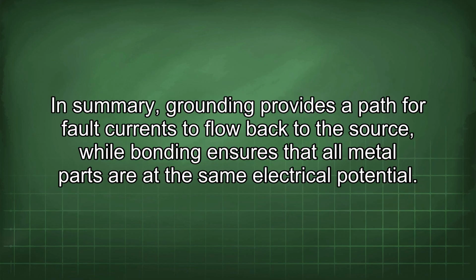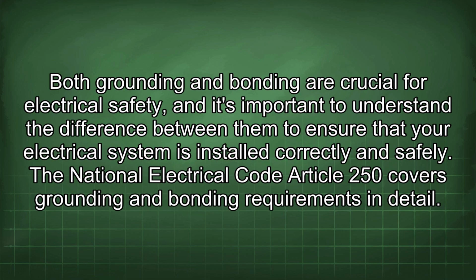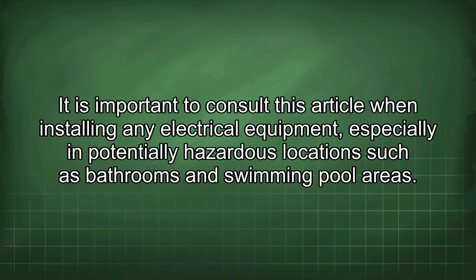In summary, grounding provides a path for fault currents to flow back to the source, while bonding ensures that all metal parts are at the same electrical potential. Both grounding and bonding are crucial for electrical safety, and it's important to understand the difference between them to ensure that your electrical system is installed correctly and safely. The National Electrical Code Article 250 covers grounding and bonding requirements in detail. It is important to consult this article when installing any electrical equipment, especially in potentially hazardous locations such as bathrooms and swimming pool areas.